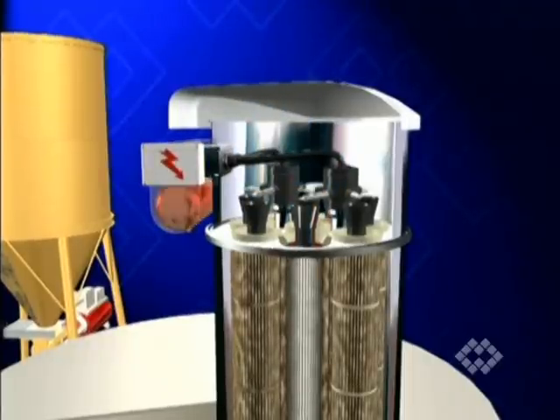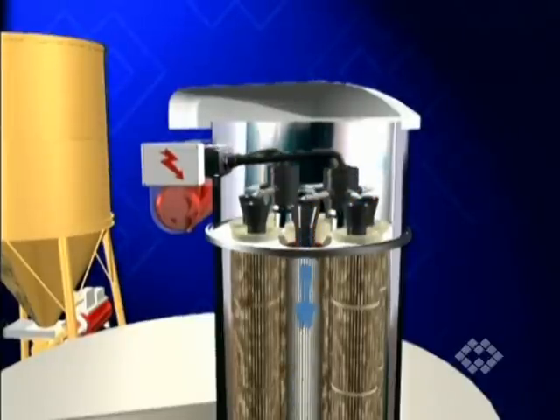To keep the media clean, groups of cartridges are cleaned alternately by compressed air jets shot inside the cartridges.